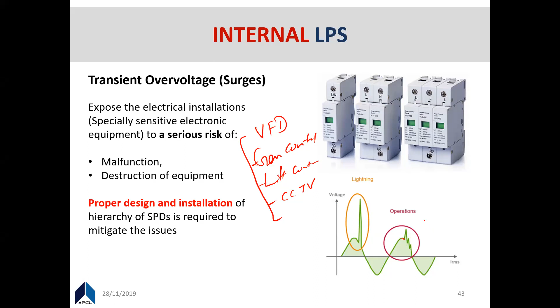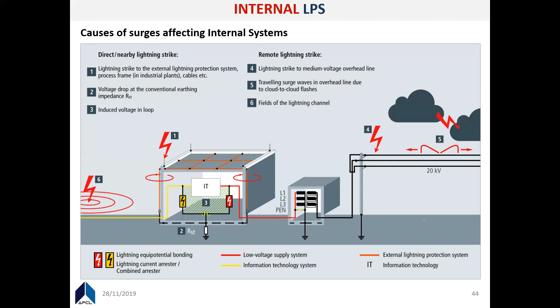It's not even a lightning strike directly to the structure; even a surge traveling through the line will destroy an entire panel. So that can even cause life-threatening issues to occupants. This is not something simple, so you have to keep that in mind. All right, so these are the switching surges. You can see the lightning magnitude, and during switching operations, when you are using switching devices, MOSFETs and all, for your switching drives and inverters, you frequently get these surges. To avoid that, you need to have surge arresters. So these are the classification of the same source of lightning strike we discussed earlier.